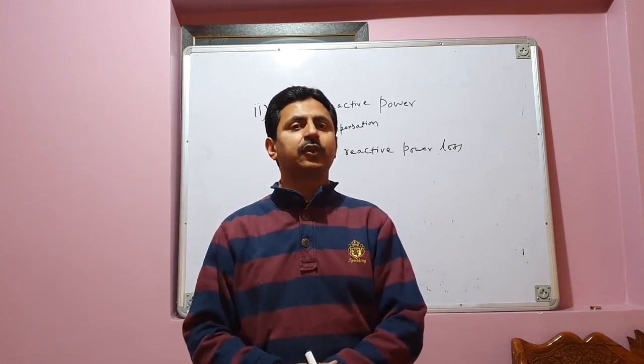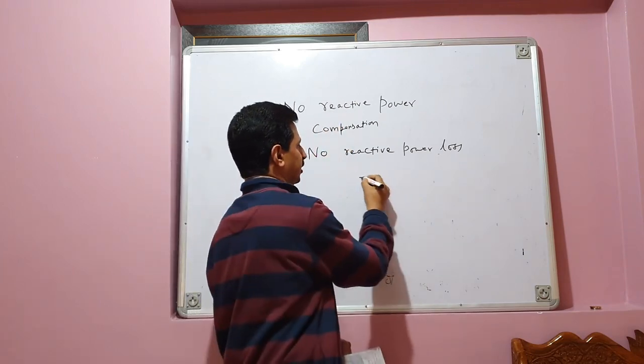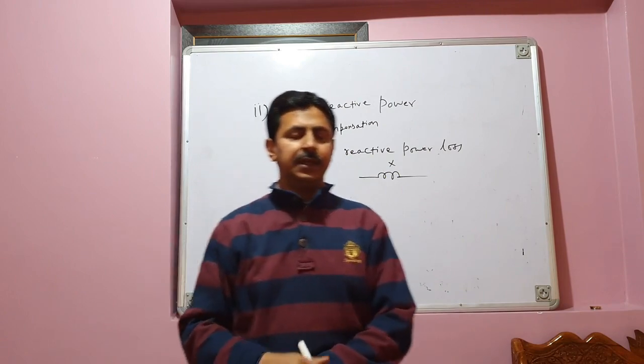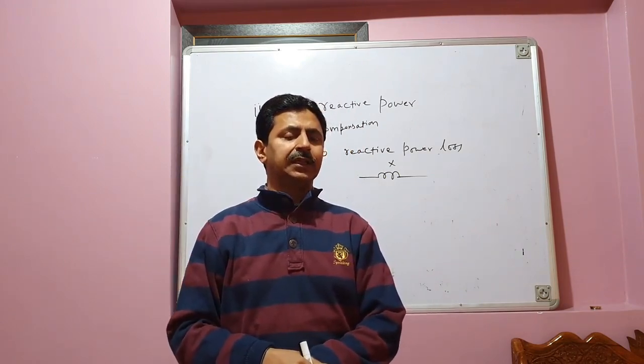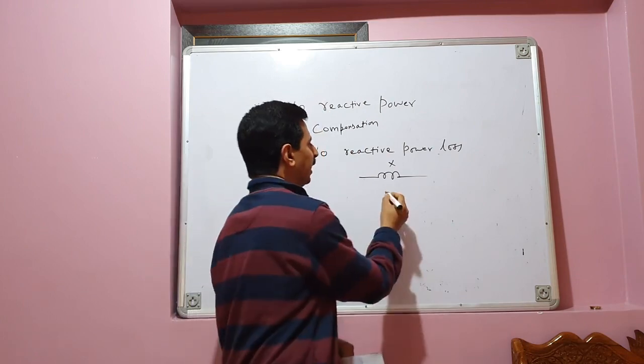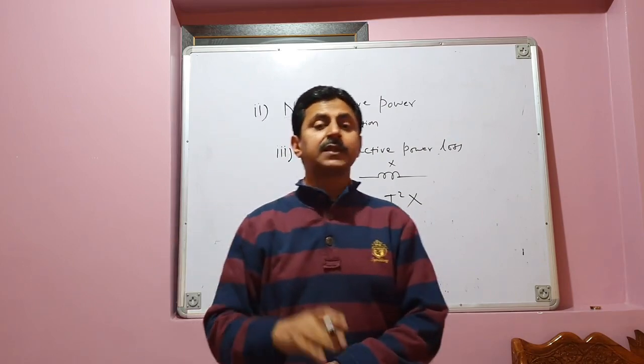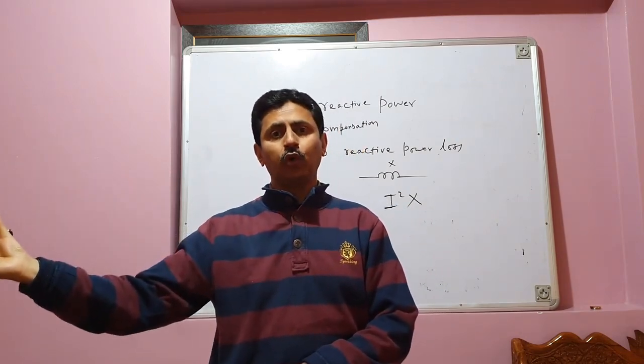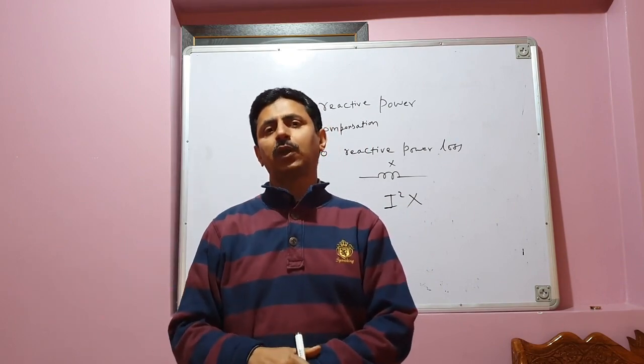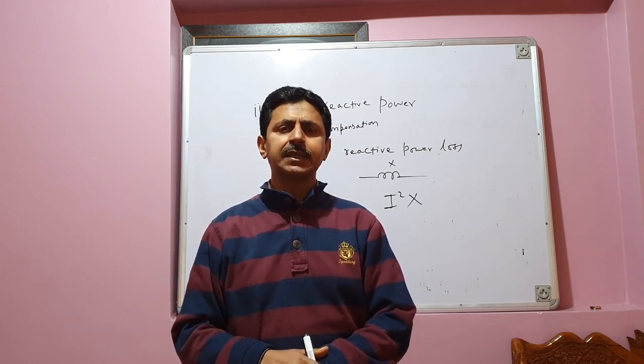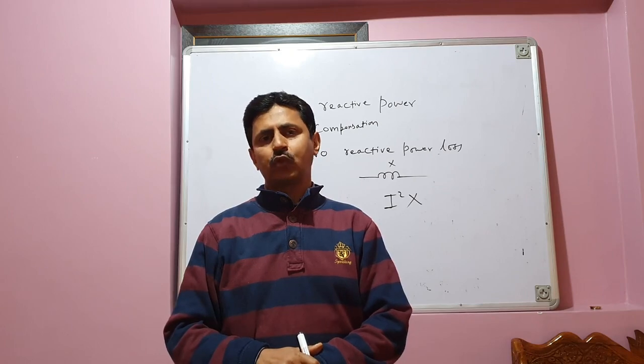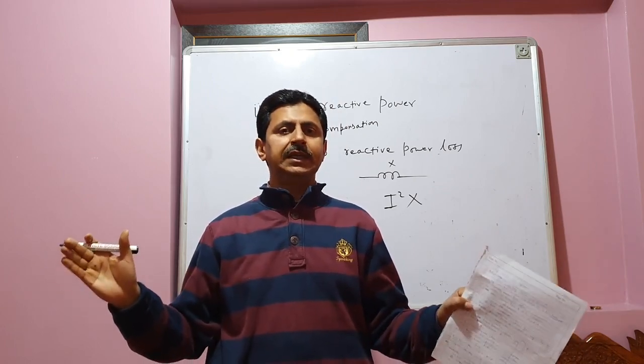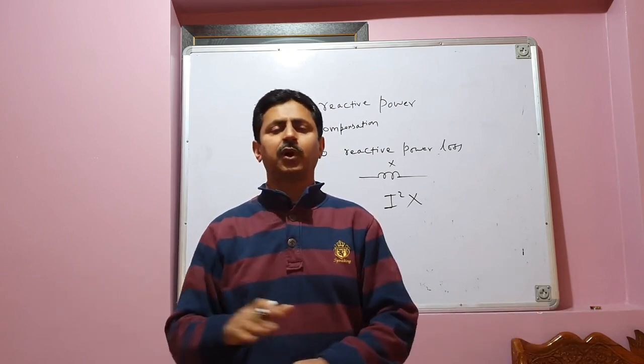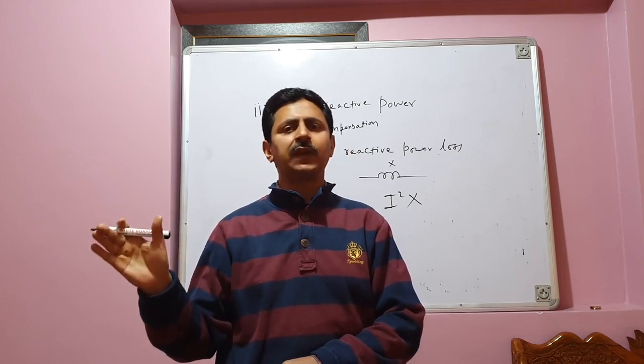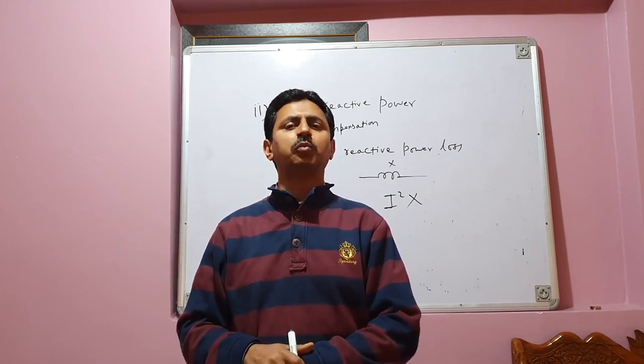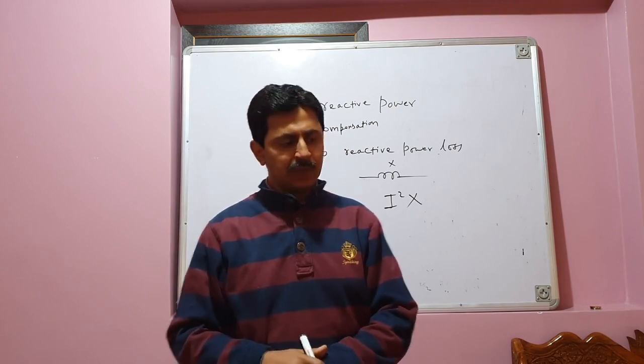And then there is reactive power loss because the transmission line has its own inductance, reactance, X. This is the reactance of the transmission line. And when current flows through this transmission line, just like you have active power loss, I square R, similarly you have reactive power loss, I square X. It is the reactive power which is not because of the load, which is because of the line reactance, and it is called reactive power loss. Do we have any reactive power loss in DC transmission lines? Answer is no, because when we are transmitting power over DC transmission lines at high voltages, in DC there is no concept of reactance. A DC transmission line will have resistance only, it will not have reactance. So therefore there is no reactive power loss in an HVDC transmission system. So therefore we are overcoming this problem also.